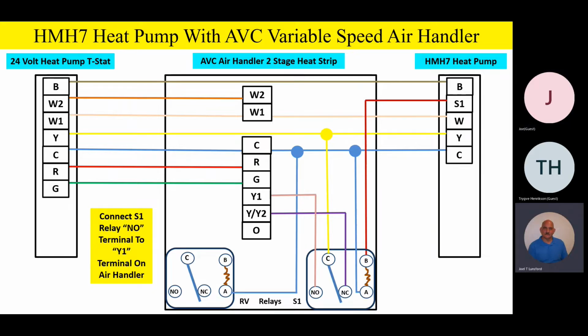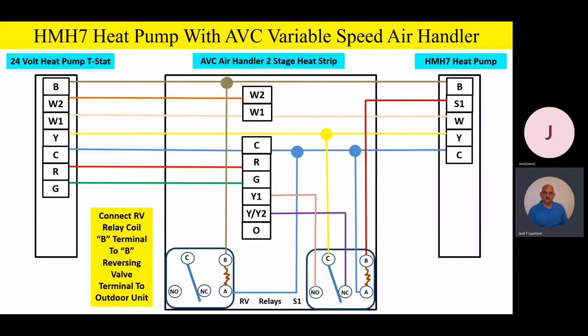But now remember, on a variable speed product, we've got that RV, that second relay we have to deal with. So the B terminal on the RV relay goes up and ties on to our B. Now what happens is this: anytime we have a call for heating on the heat pump thermostat, that B terminal is going to be energized. That B terminal is going to be energized for reversing valve operation on the outdoor unit. At the same time that happens, it's going to energize that RV relay coil you can see in the block diagram.